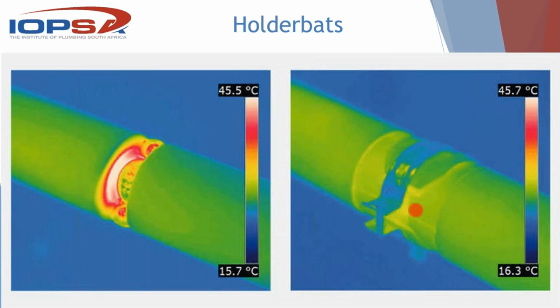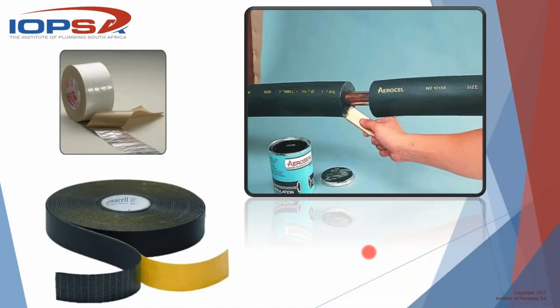Okay, just generally, once the lagging has been installed, how do we join it? We've spoken about glue, like you see here. There are other methodologies of bringing those two surfaces together. If you talk about this expanded nitrile rubber, I really do prefer the gluing method. It's an easy method, even on site. There are some instances where it is tricky, with funny little angles involved, and you can't keep it apart long enough for the glue to become untacky, because we know your contact adhesive needs to dry for 5 minutes before you bring it together.